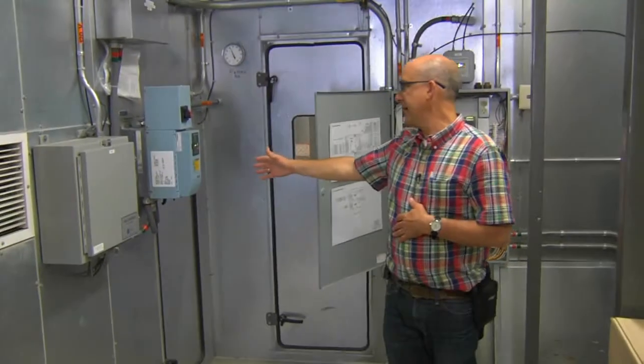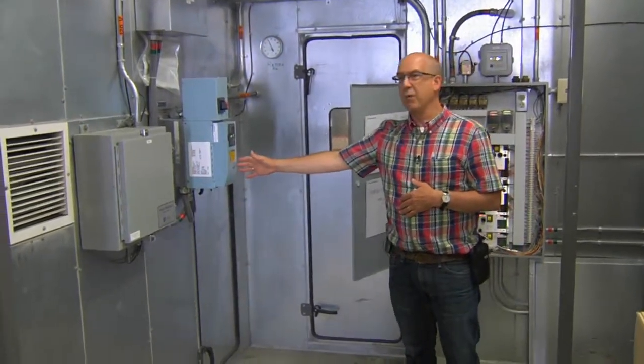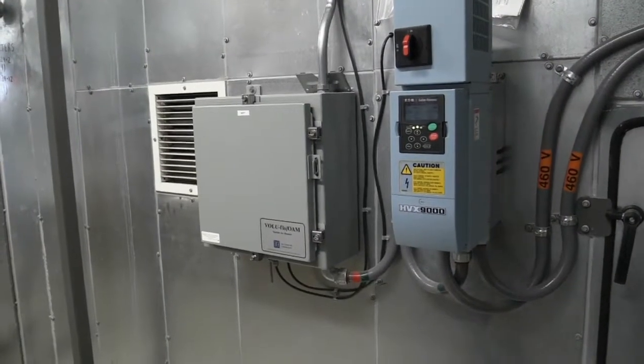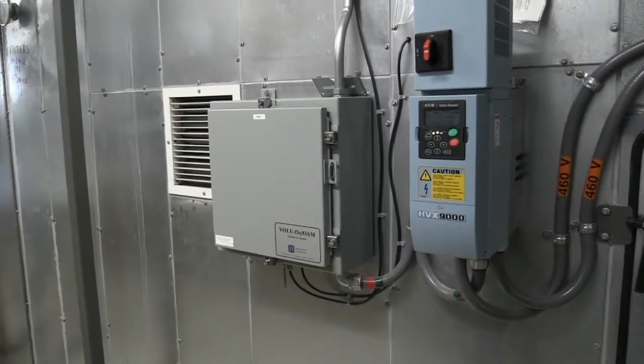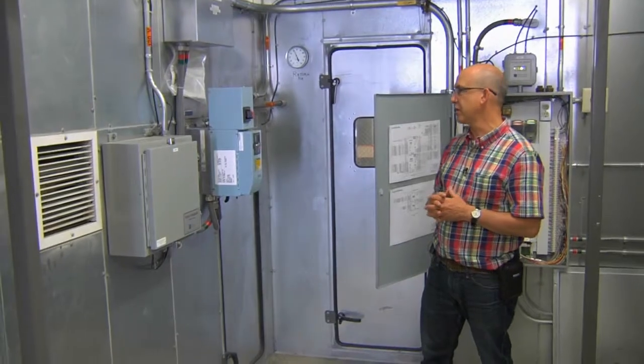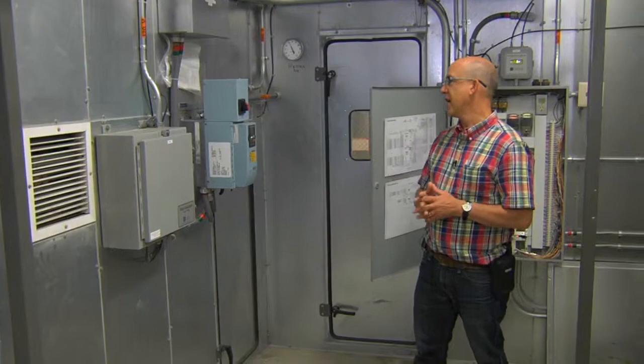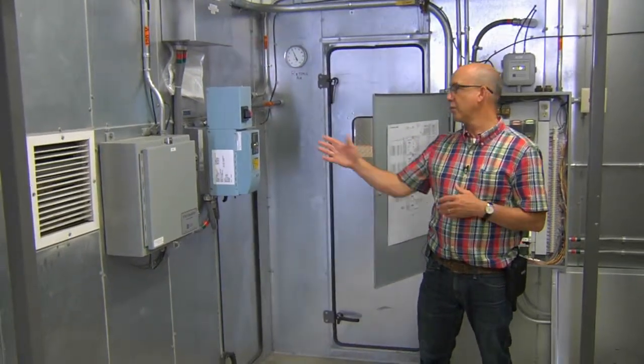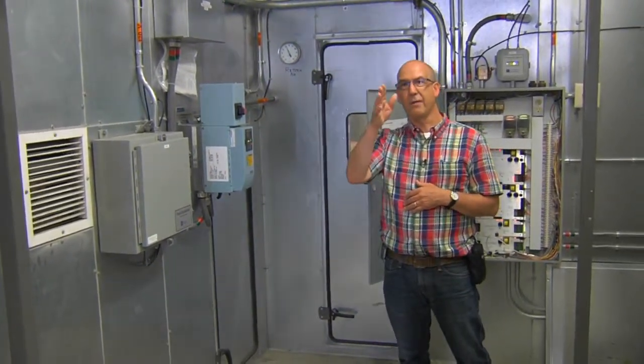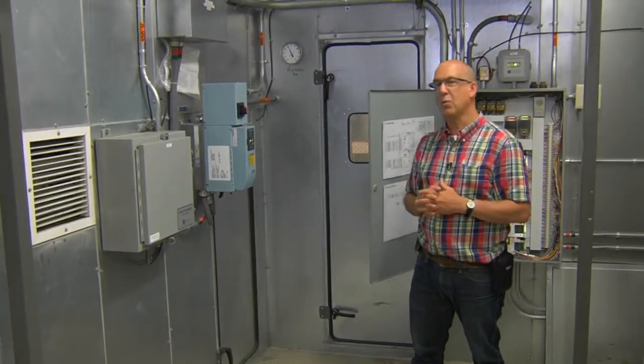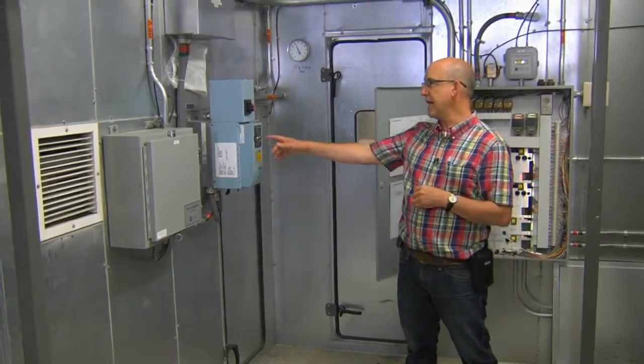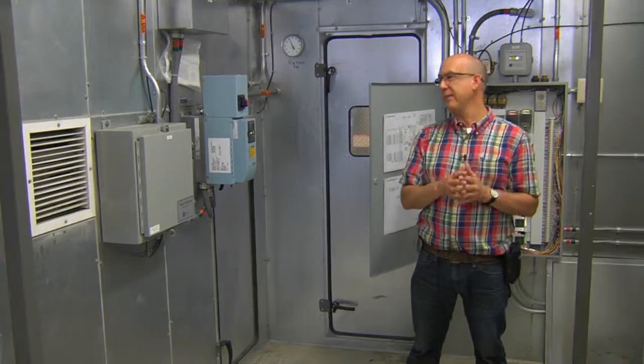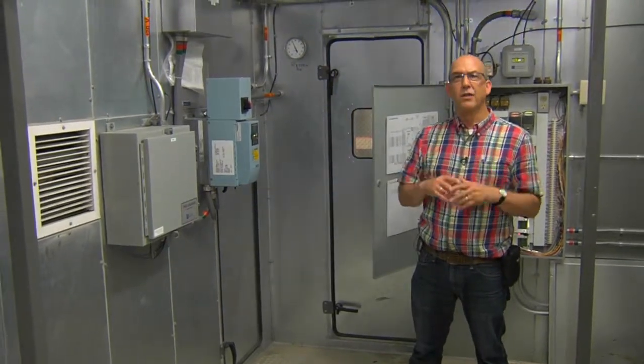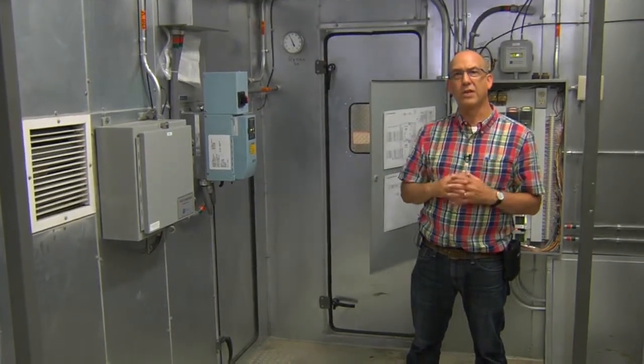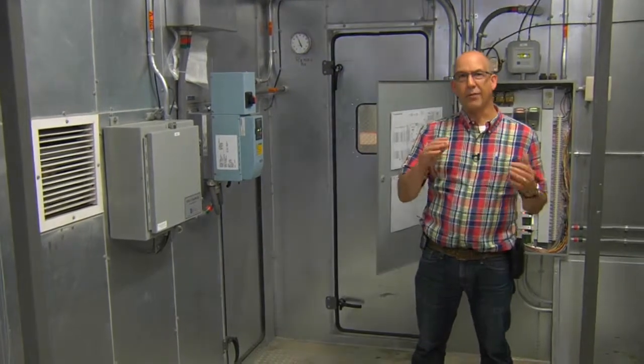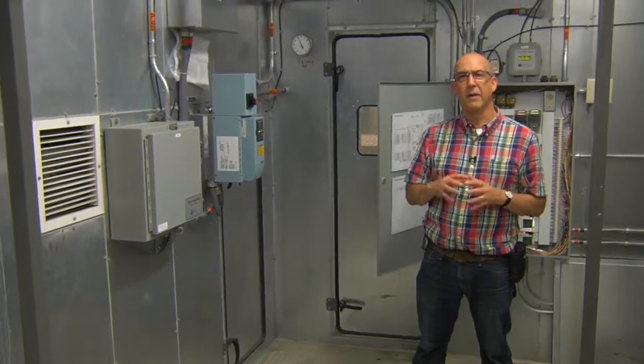Right here on my right, we have a VFD, and we can look at the screen. It has an output reading of the speed of the fan. It's very stable. That indicates really good control for the return fan. The two supply fans that run in tandem with the return fan, their VFDs are behind us about 20 feet. And we notice that the readout on the screen for the supply fans is varying about 3 to 4%, or 3 to 4 Hertz, I should say, over about a 30-second period, which indicates a little bit of instability.